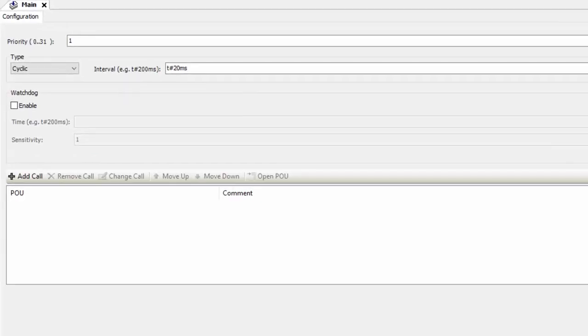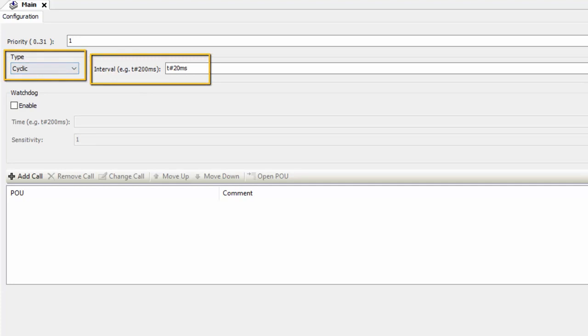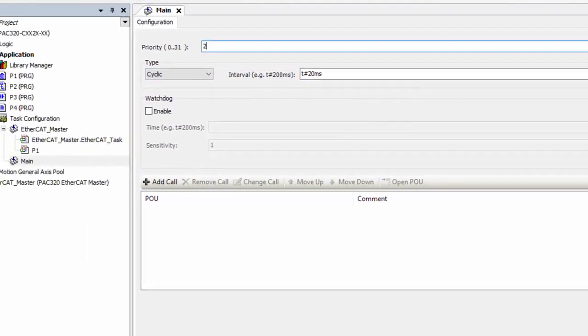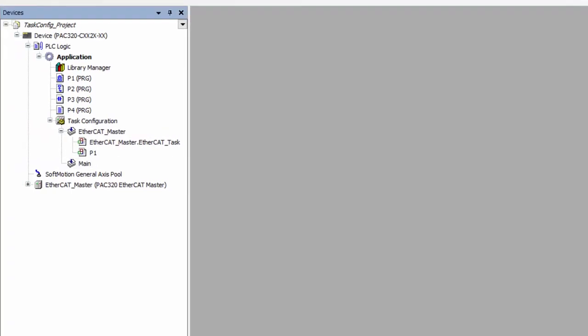To configure this new task, simply double click it. We will set its type to cyclic and its interval to 20 milliseconds. Since it's going to be handling our general PLC logic, I'm going to be changing the priority to two.